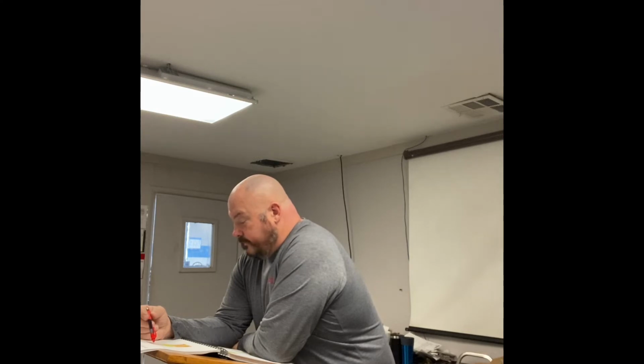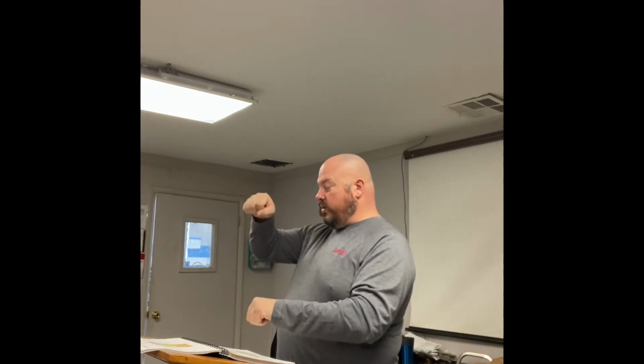So, what's going to happen is there is a valve to keep the high pressure from bleeding back to the low side. And there's also another valve on the other side of the head that keeps the high pressure of the line from bleeding back into the cylinder when the piston goes down. Now this is a reciprocating compressor. That piston is going to go up and down. We call this top dead center, or TDC. When it is top dead center, that means that piston is all the way up. It's on a crankshaft, just like a crank on a bicycle. When it's all the way up, not partially cocked one way or the other, straight up and down, that's top dead center.